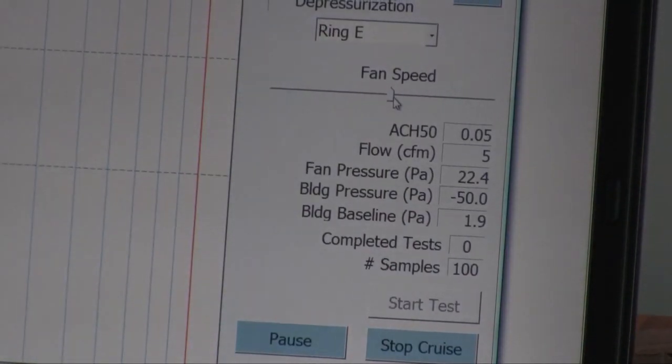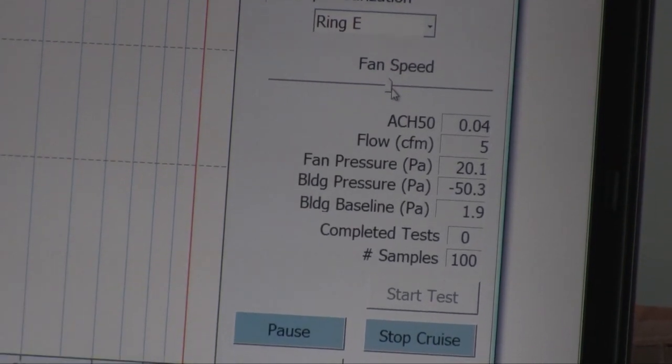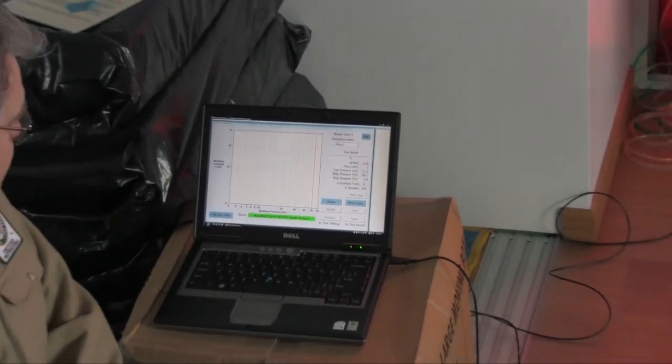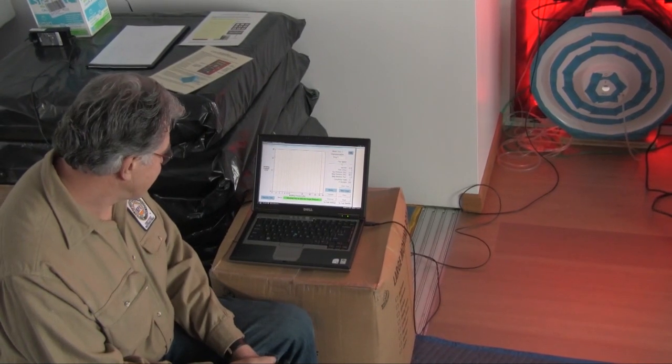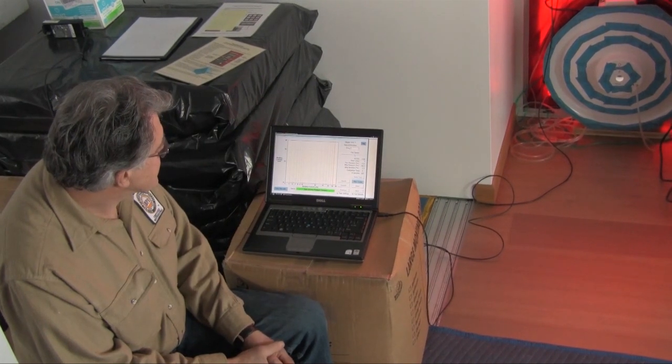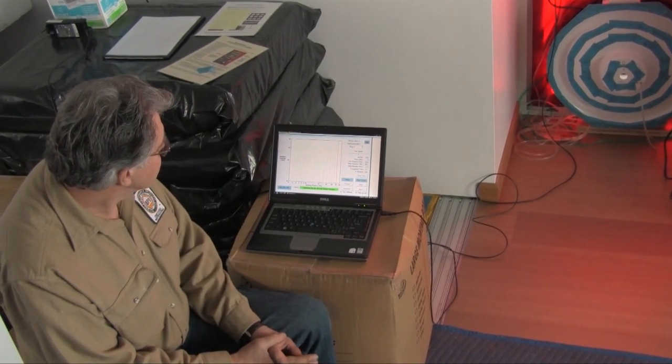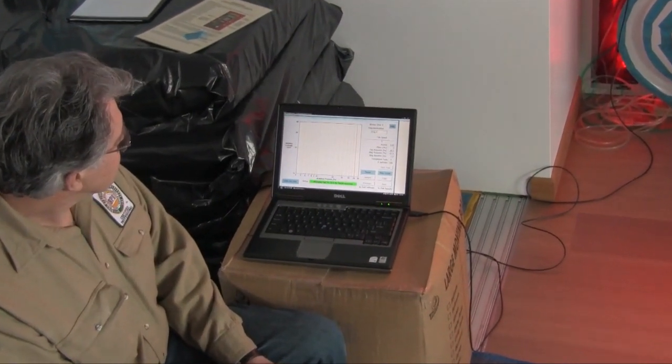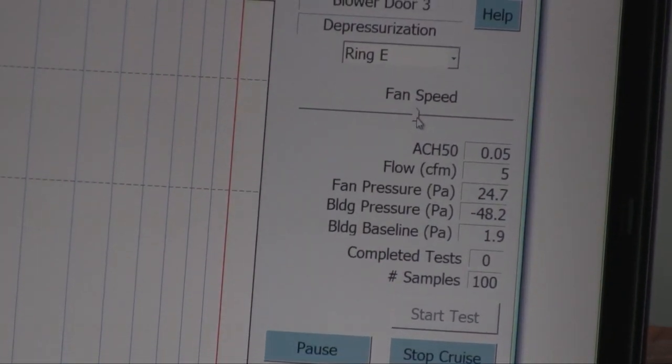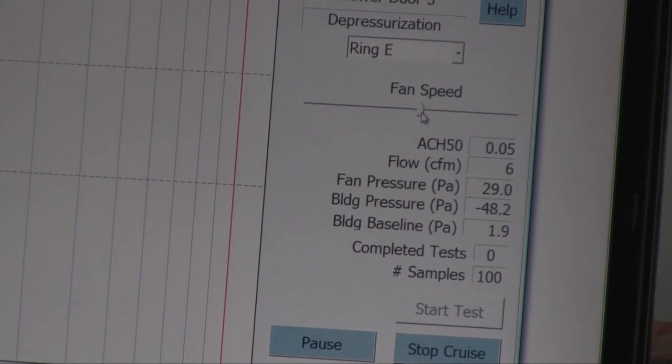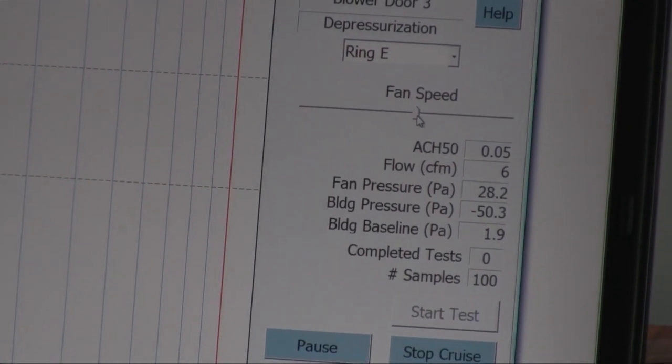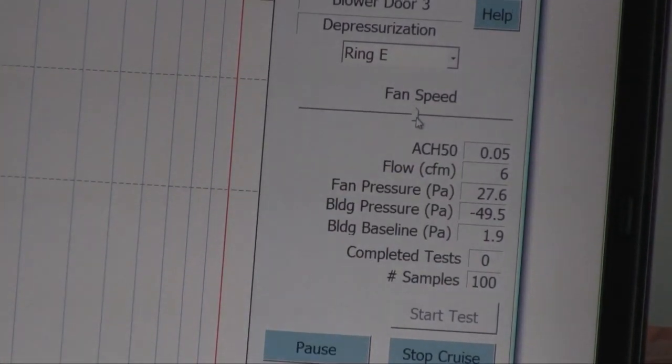Now all the air that goes out through that hole, the 5 cubic feet per minute, is all the air that is leaking in from all leaks everywhere in this house. That's not much. It will continue to search a little bit because there's a little bit of a breeze outside, which will vary things slightly. The fan flow jumped up to 6 cubic feet per minute.